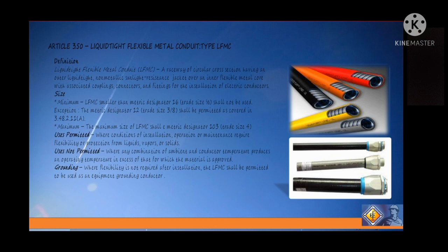Next is for Article 350. It is the liquidtight flexible metal conduit or the type LFMC. The type LFMC is a raceway of circular cross-section having an outer liquidtight, nonmetallic, sunlight-resistant jacket over an inner flexible metal core with associated couplings, connectors, and fittings for the installation of electric conductors. So makita natin yung itsura ng ating type LFMC sa ating picture at the right side of our slide. So for the size ng ating LFMC, for the minimum, LFMC smaller than metric designator 16, trade size 1/2, shall not be used.